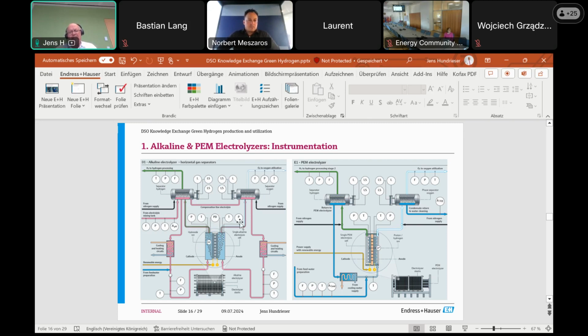On the other side we have oxygen, and oxygen applications require cleaning, but cleaning alone is not enough - that might be enough in an automotive factory where you don't have hydrogen in parallel. You need cleaning and listed materials. In Germany we call it Bundesanstalt für Materialforschung, the German federal institute for material research. Materials for oxygen have to be listed and the site has to be cleaned.